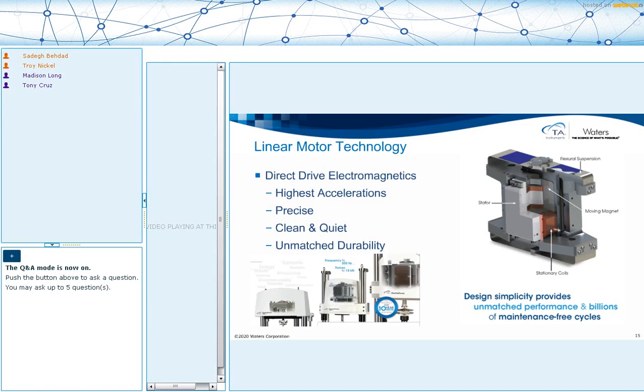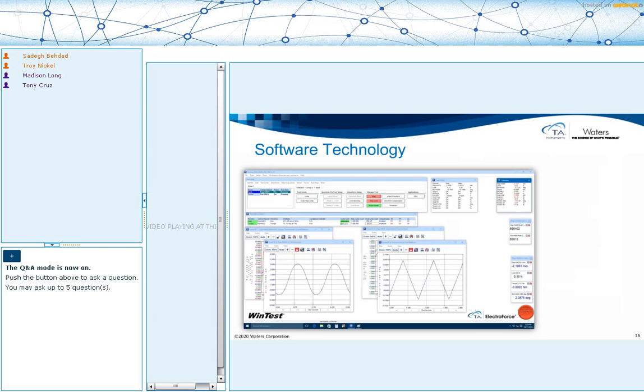So this direct drive electromagnetics allows us to have very high accelerations because there's no bearings, and it is very precise because by controlling the current we can control the mechanical movement. It's very clean and quiet, and it has unmatched durability because of its frictionlessness. So we have a lot of these instruments placed in animal labs or even in clean rooms because of their quiet performance. And in medical devices specifically, the durability and the precision is what matters most.